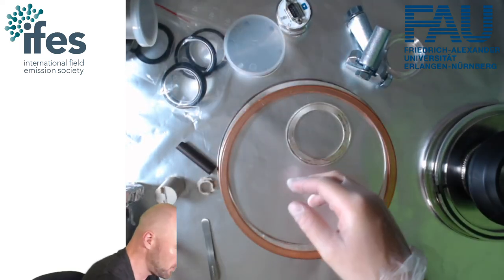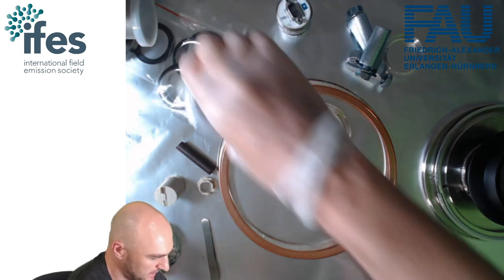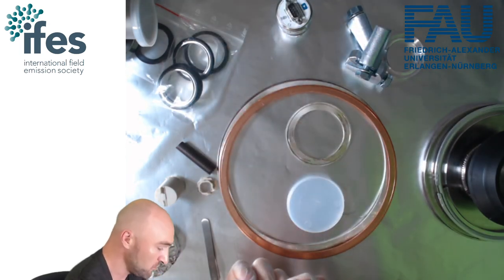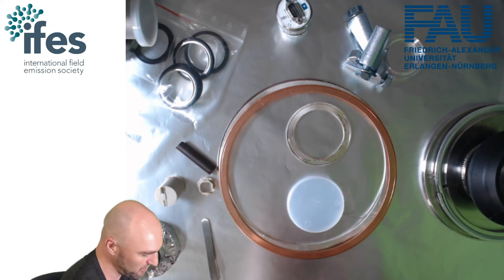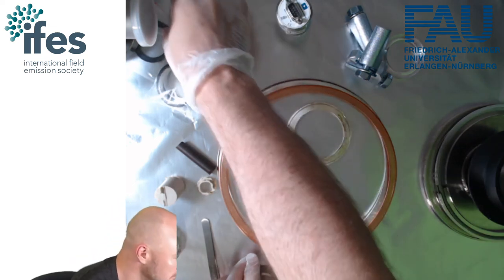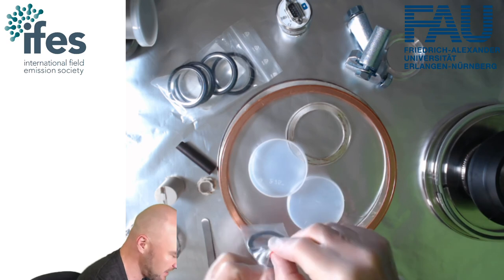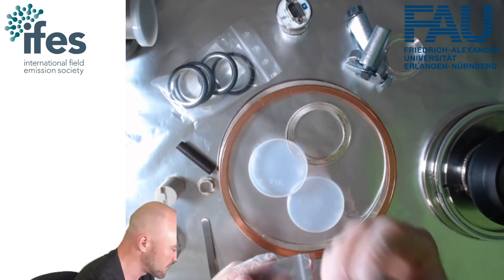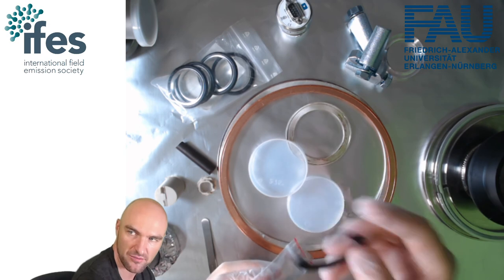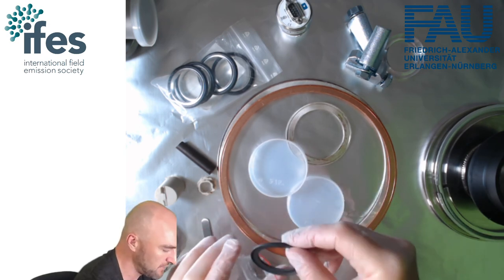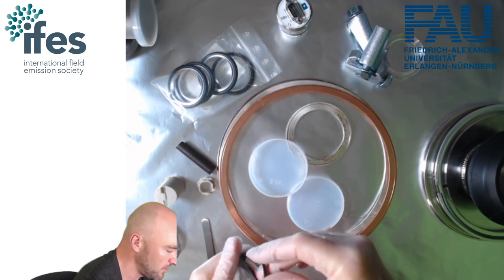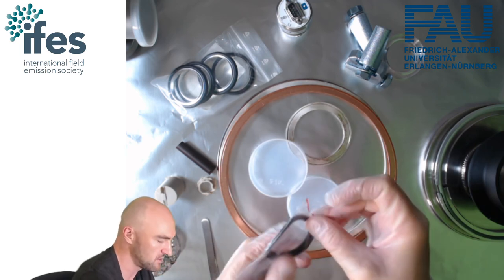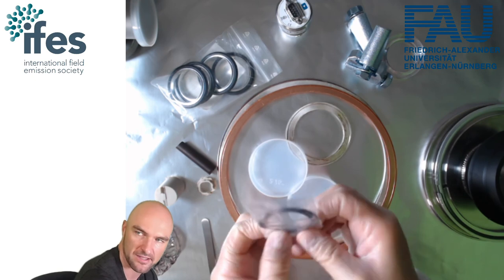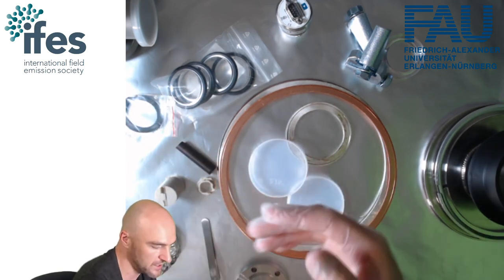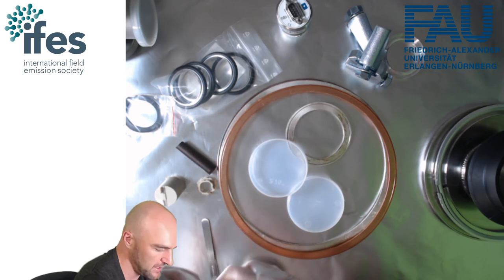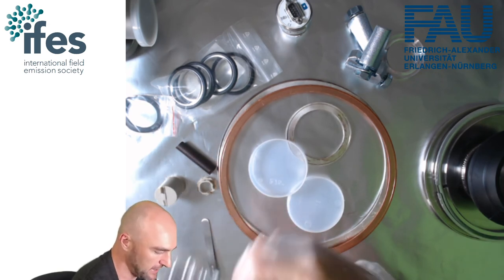And then when you put the gaskets together, sorry, I don't have a CF. I do have a CF40 here, actually. So what I've shown you is just CF flanges with metal gaskets, but you can actually get rubber gaskets for CF flanges as well. This is just if you have a CF part somewhere and you don't need super high vacuum and you don't always want to throw away all the copper gaskets, then you can use some neoprene gaskets, some Viton gaskets as well that you can buy. Of course, then you lose the advantage of bakeability. So you can't bake anymore then.